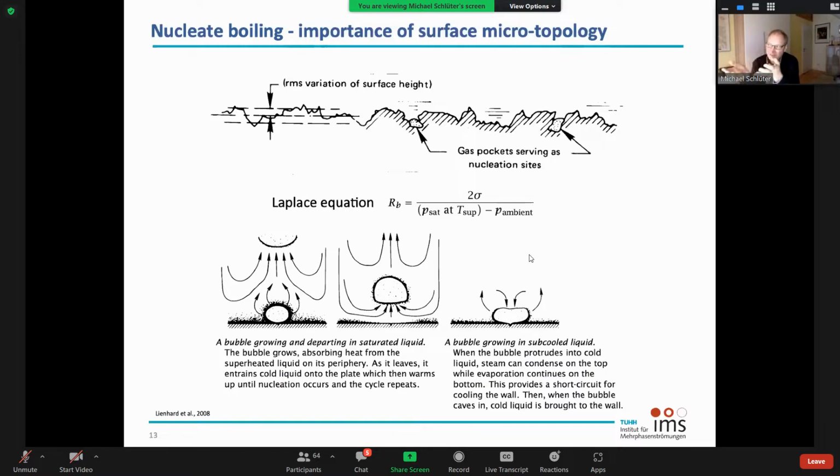And if you have one bubble that is created, then you get a lot more tiny bubbles, and more and more nucleation sites appear. So you will get a very, very rapid overboiling of your system. It's like an explosion. Suddenly the whole water shoots out of your system with a temperature of 120 degrees. You can imagine this is really dangerous in the laboratory, and you should definitely warn your laboratory staff not to do that.